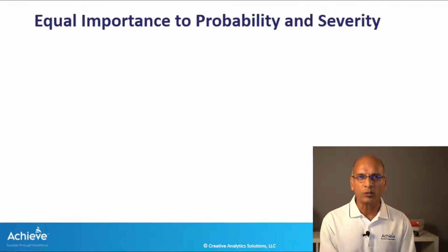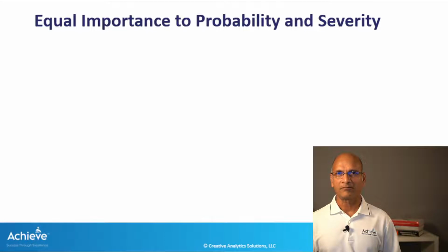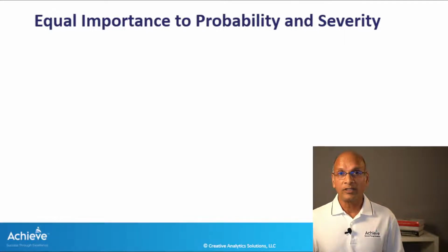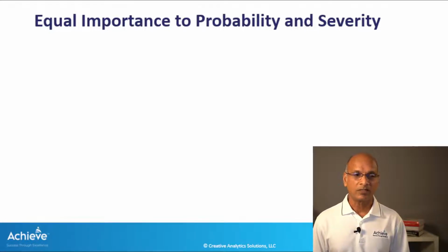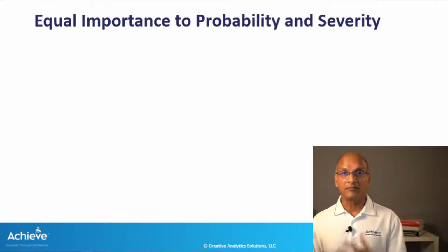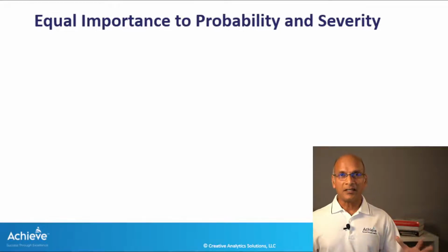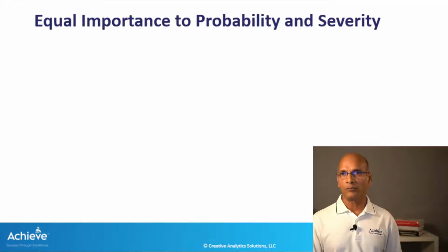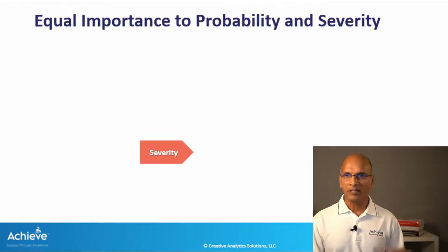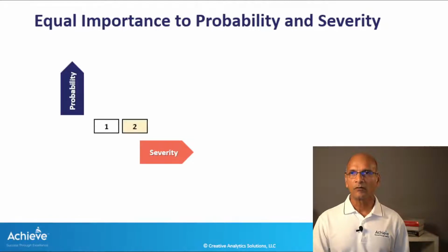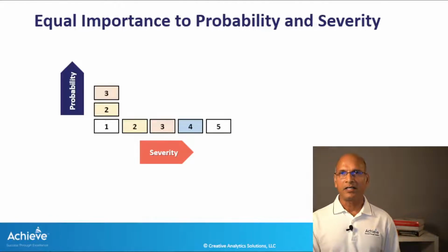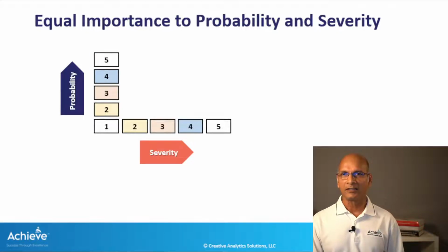We need to have equal importance to probability and severity. There should be equal weight when we combine the two. ISO doesn't say to treat probability any differently than severity. They are independent of each other and they should be given equal importance. So let's play out a scenario. We have a 1 to 5 scale for severity and a 1 to 5 scale for probability. When severity is 1, you can have 5 scores for probability, and when probability is 1, you can have 5 scores. You're just multiplying the two numbers.